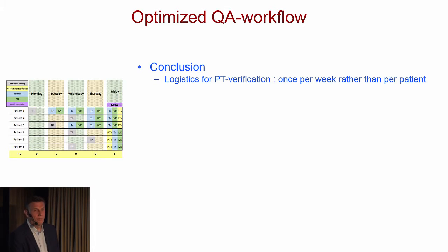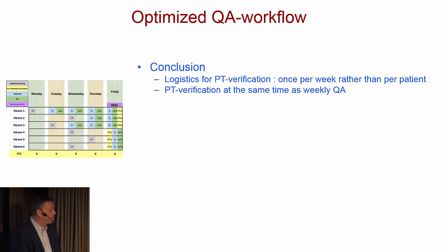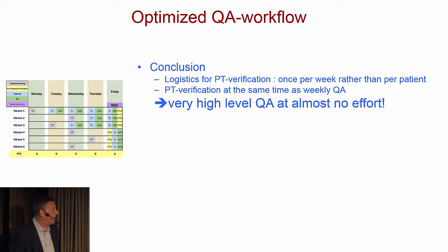So to conclude this, the logistics for the pre-treatment verification, once per week rather than per patient. So this is a big simplification, and you will save a lot of time. If you do the pre-treatment verification at the same time as weekly QA, you will save even more time. And still very high level QA at almost no effort. So you get the best of two worlds, the efficiency and the accuracy.